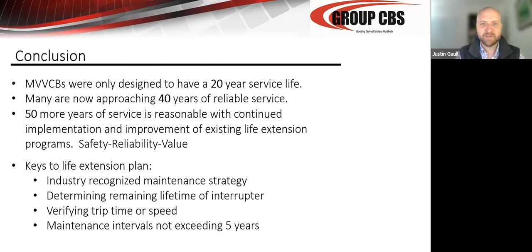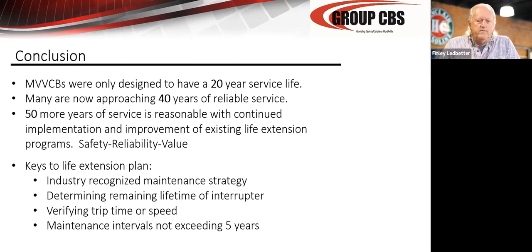Is it possible to identify a bad vacuum tube prior to opening the breaker? This gentleman had one about 5 years ago arc to ground due to a bad vacuum tube, but we didn't know until the breaker was opened. If you open the breaker offload, you're not going to have that problem, and you can test it. If you're opening it with a big charging circuit, for instance, a long cable or something, then you understand the failure you can have there. There's no way to test the breaker for loss of vacuum with it closed in the circuit currently.